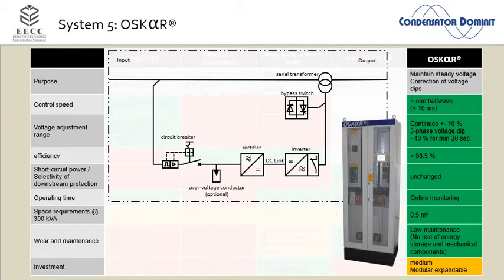Berkeley University says the average UPS they tested, really at the university in California, has an efficiency of 92 to 94%. That is not the data sheet value of the manufacturer. That is tested by the university. So that means I have 6 to 8% additional permanent losses. If I run a plant with several megawatts, nobody wants to pay another half a megawatt of losses, even not in America where the power is cheap, definitely not in Germany. So that was the big thing: do not reduce the short circuit power here.